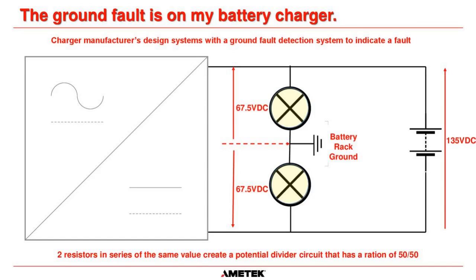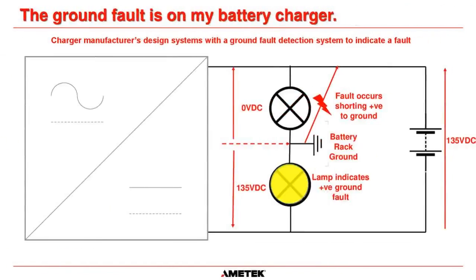So how does this system detect a ground with this very simple 2 lamps? Well, let's say the positive has a short to ground. So now ground is at the same potential as positive. That means the voltage across this lamp goes to 0 volts because it's the same point. But look what happens across this lamp. Now the voltage has gone to the full system voltage, 135 volts. So what happens to that lamp? It turns on, and the lamp indicates that you have a positive ground fault.